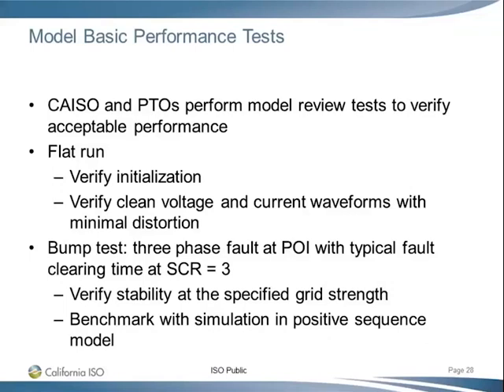So for the bump test, it needs to be stable. Also, we will compare the bump test against the positive sequence model test. So they will never be the same, but as long as there's a pretty reasonable match, like you can see within the same time frame the P and Q recover, and the general trends during the transient are the same, that will be fine. If we see some significant discrepancy, we would ask for explanation. Some discrepancies are reasonable due to model limitation. Some could be modeling error.